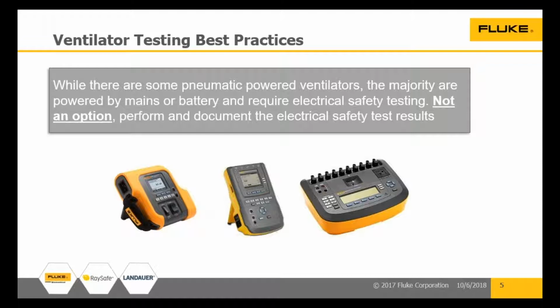Whatever the manufacturer specifies. So in some cases, they will specify IEC 60601-1 because they're worried about their design validation testing and what they're doing in the production final assembly test and in their service depot. Okay. And when they roll it out to their field service organizations, sometimes their quality manager doesn't understand that they could really do with 62353. There's a testing method there that matches up and correlates pretty well with the IEC 601-1.